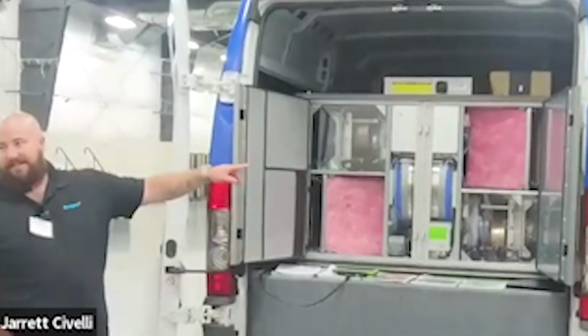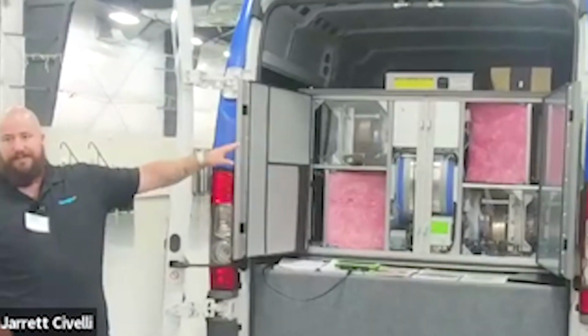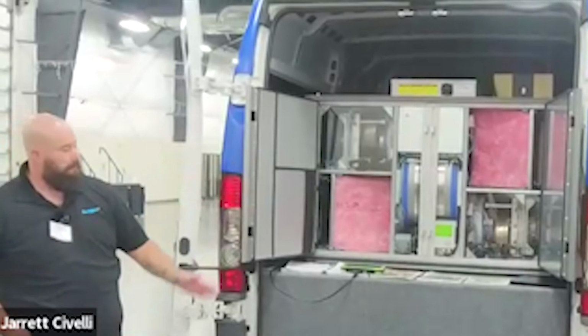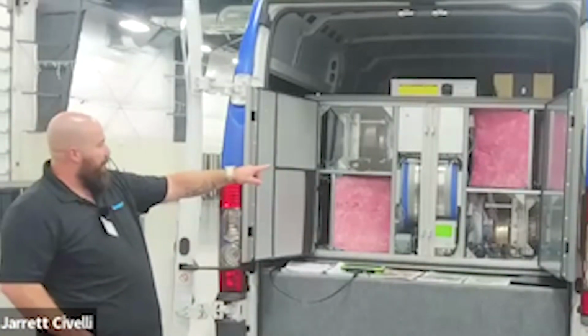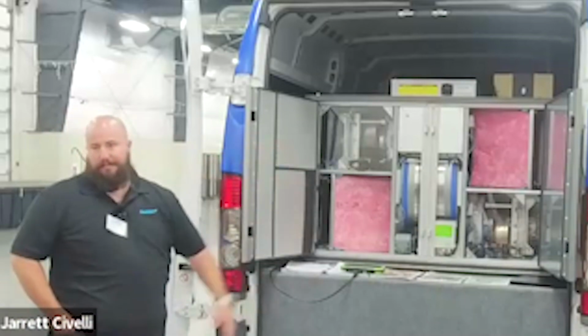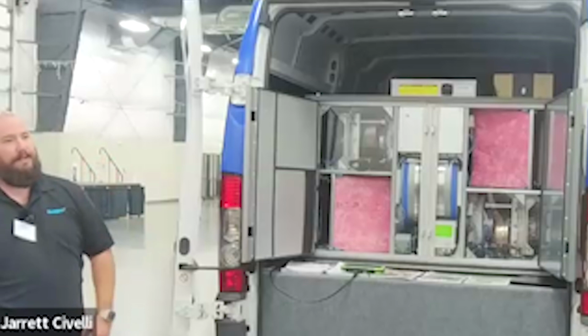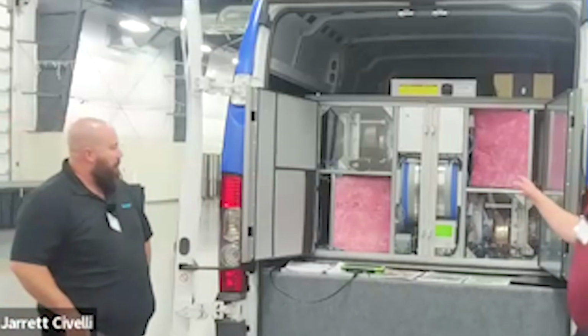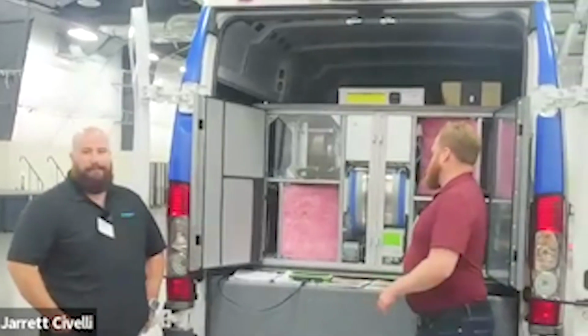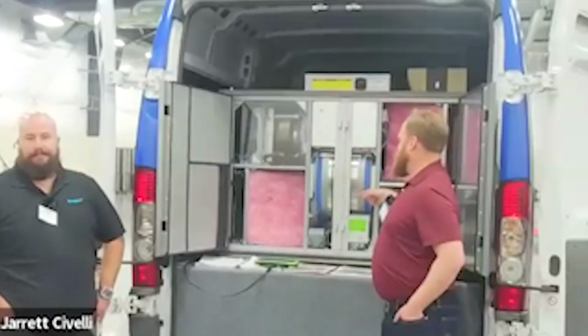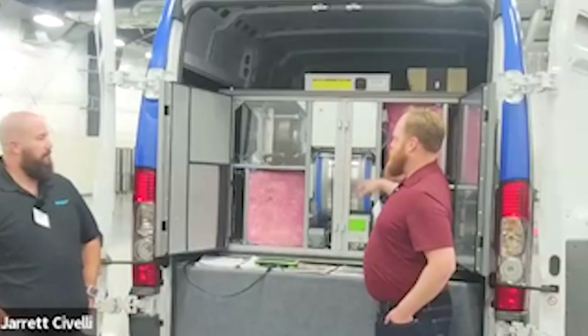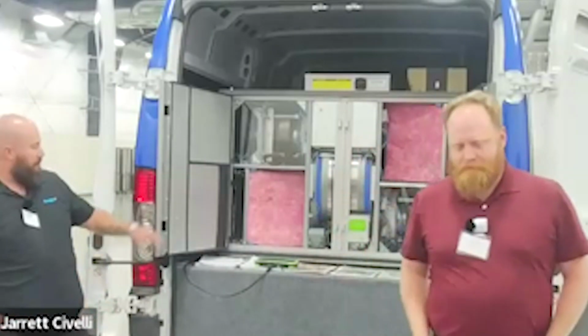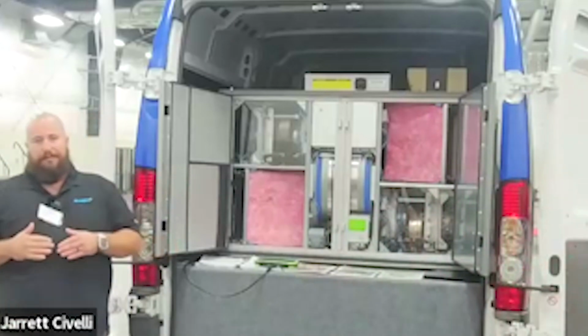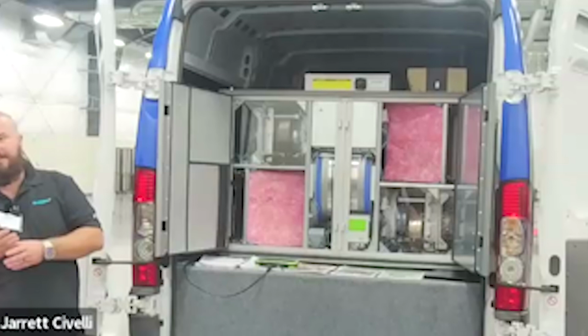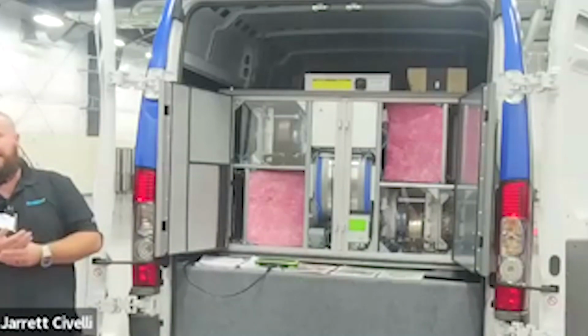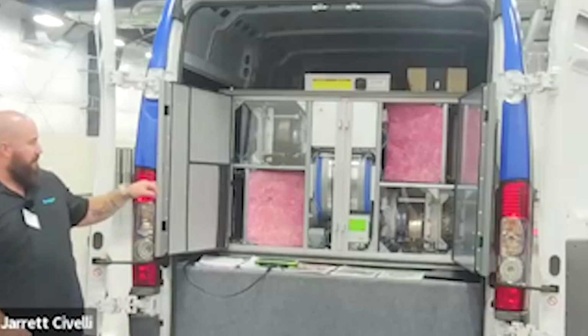For most of the HVAC guys, it seems kind of wonky to have a filter there. The filter is really just to protect the wheel. So same thing, MERV 13 bag filter. We have our wheel, another ECM motor pushing air out of the building. I mean, you have two different paths, and those airstreams are crossing as this wheel is turning, and you're exchanging heat between the two airstreams. It's just a mesh of aluminum. That aluminum picks up that heat, and as it rotates slowly into the other airstream, the heat's given back to the space.